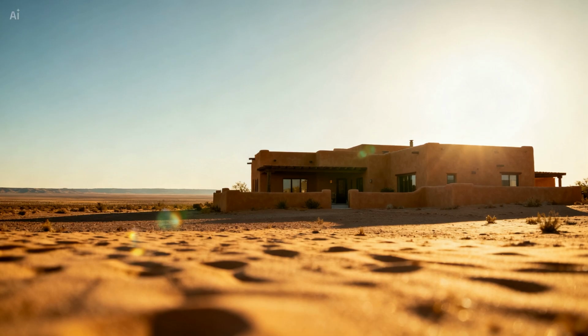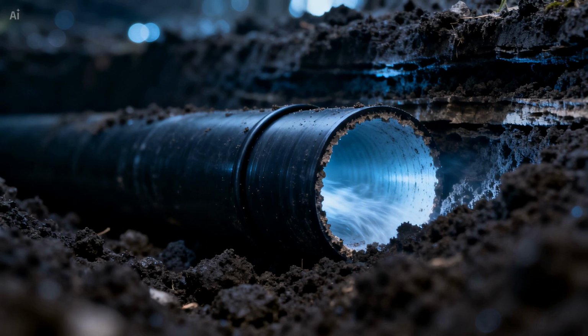Because understanding when earth tubes work brilliantly and when they do not is the difference between a successful installation and a disappointing one. Earth tubes work best in hot, dry climates. The American Southwest, the Mediterranean, the Middle East, Central Asia, arid regions of Australia and Africa. Any environment where daytime temperatures soar but ground temperatures remain in the low to mid-50s. In these climates, the temperature differential between surface air and ground temperature is enormous, and the air entering the tube is dry enough that condensation inside the pipe is minimal.